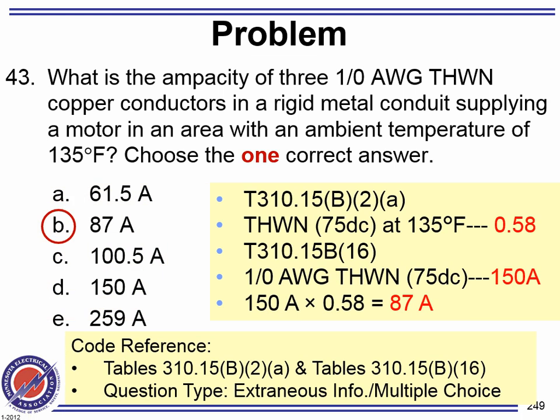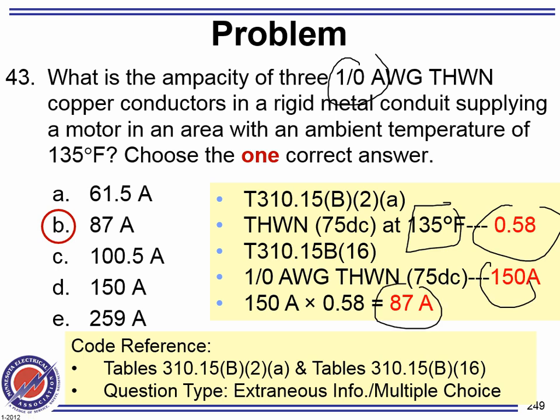Here's what we're going to do. So, an ambient temperature, gentlemen. Let's see here. There is 1/0, three conductors, 1/0. Based on this ambient temperature, gentlemen, you've got this. 1/0 can give you 150, so your conductors are limited to 58%. So 87 amps. Any comments, guys, questions about that?